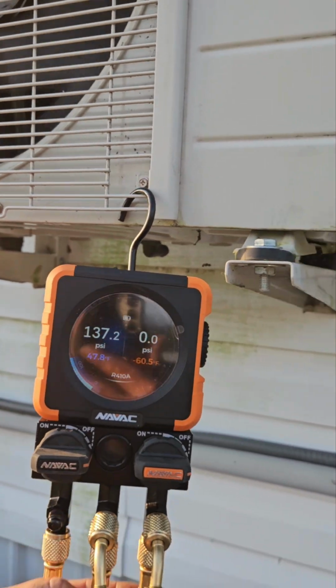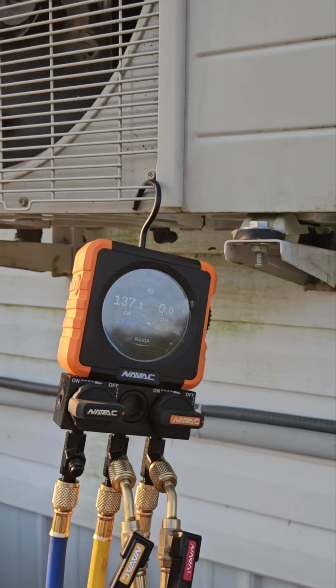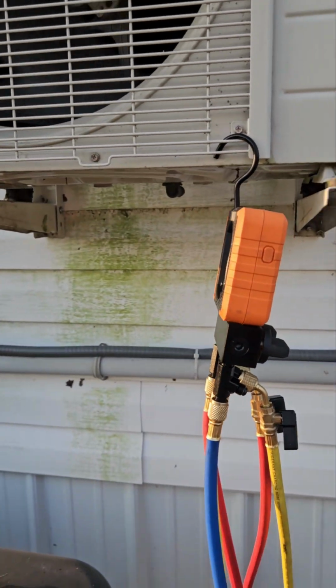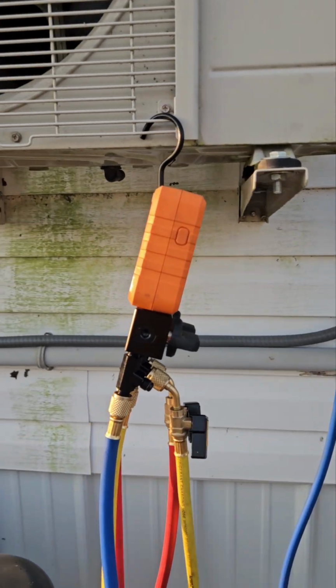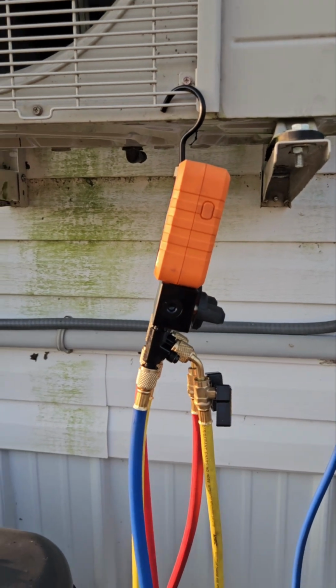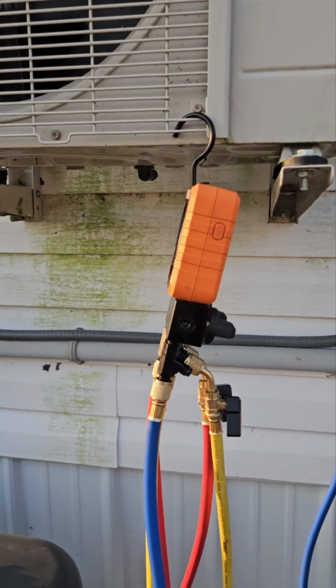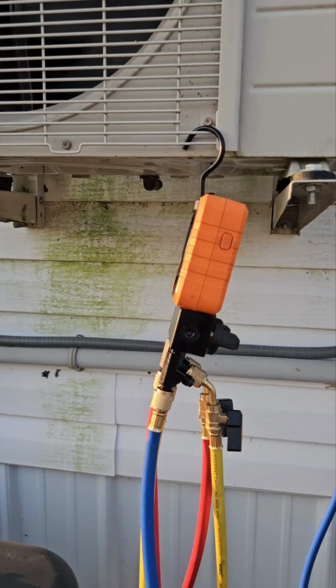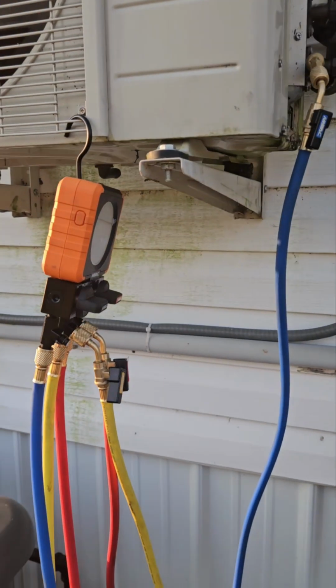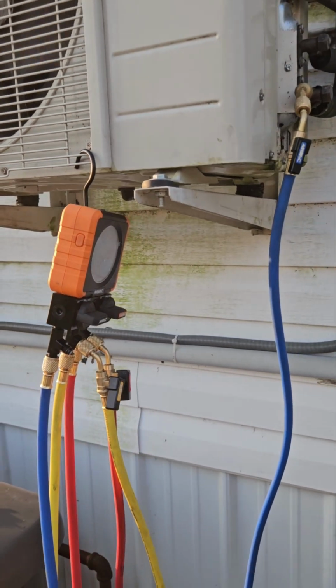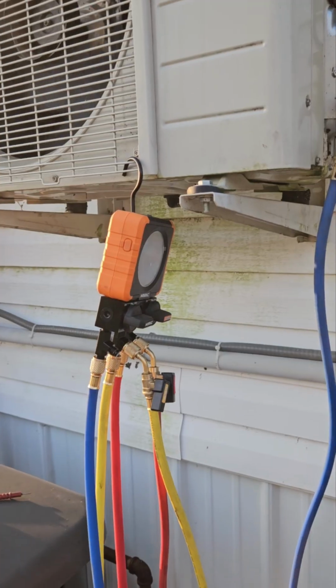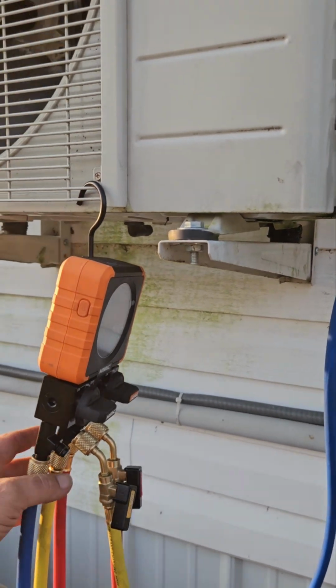I would love for it to just be that thermistor not in its holder in the coil. And what a thermistor is, for anybody that don't know, is basically a temperature probe. It takes temperature and gives the control board a resistance value, and that equates to temperature. So basically it's an electronic thermometer.